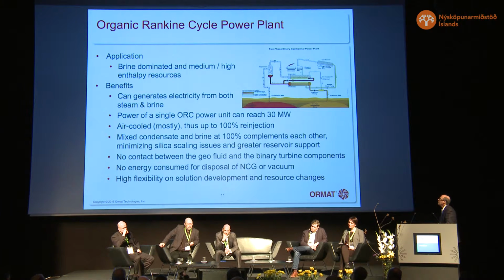The binary is used generally for brine-dominated or high and medium enthalpy resource where we have a two-phase. It can generate electricity, as I said, from both steam and brine. Today, as the lecture before, the size of an ORC can reach up to 30 megawatts. I'm sure that in the next few years, it will approach 40 megawatts. Mostly air-cooled, thus 100% reinjection.